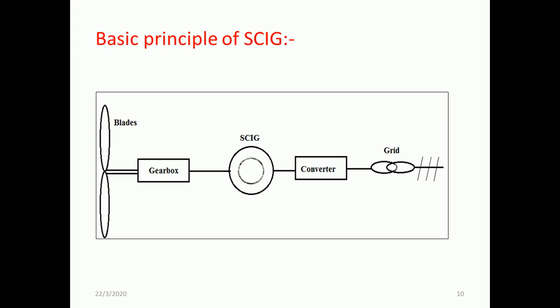So we'll take one generator at a time. We'll discuss the squirrel cage induction generator. As discussed earlier, the squirrel cage induction generator can be used in the wind energy sector. Further, this is the topology of the basic principle of a squirrel cage induction generator. You can see that it is employed with a gearbox. The gearbox can have various ratios, for example 1:98, which can be used to maintain a steady output.